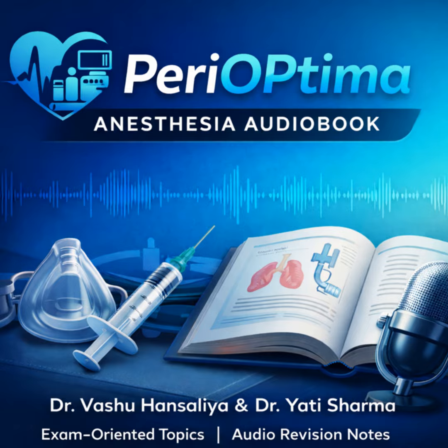And expiration. During expiration, the pressure drops. The lungs passively deflate, pushing gas through the expiratory limb and into the absorber. The key distinction here is that the pressure generating the tidal volume is controlled externally, and the APL valve's function shifts from managing continuous flow to managing peak pressure and venting during the expiratory phase. This inherent complexity gives rise to the system's specific advantages and disadvantages.